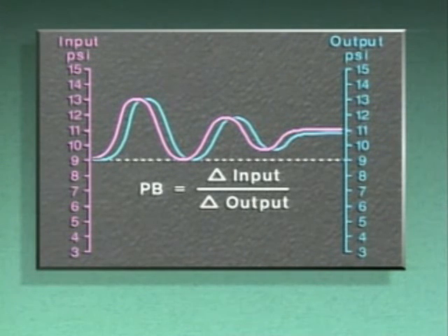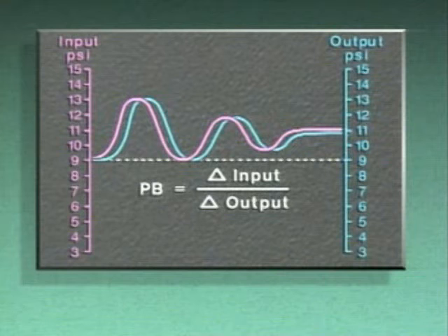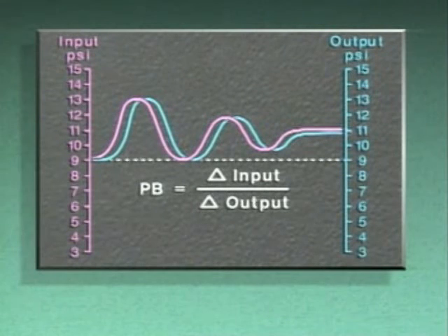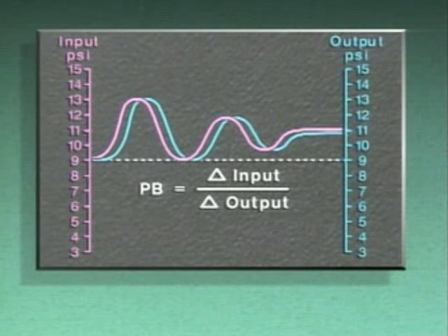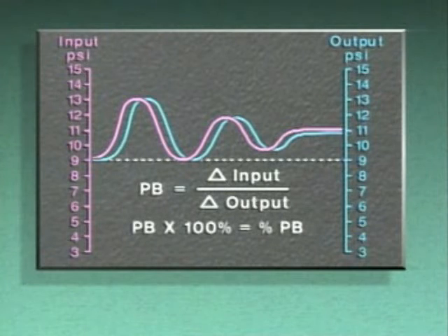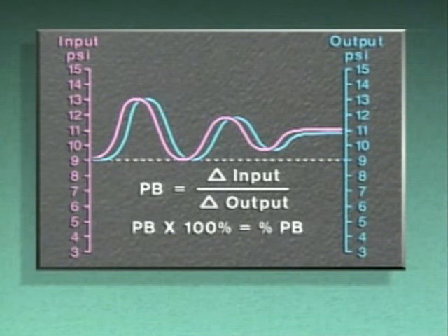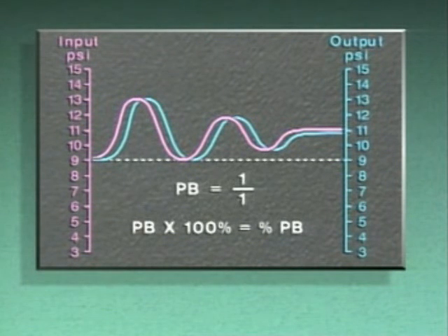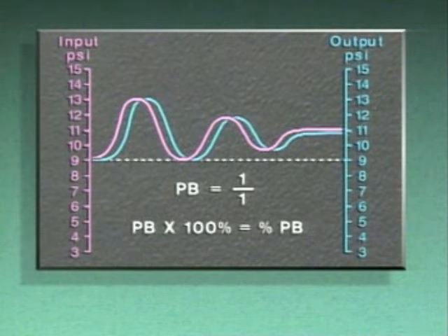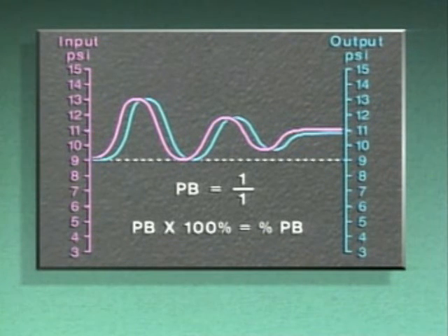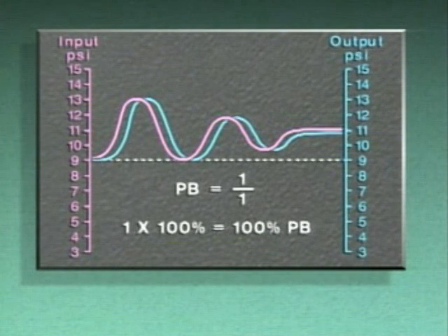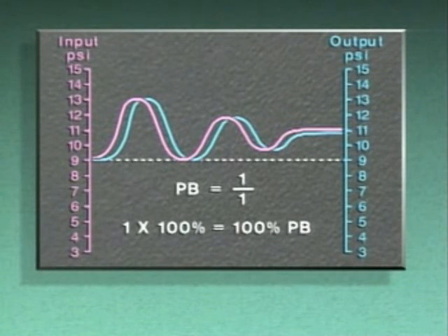Proportional band is the amount of output change, or delta output, in relation to a given amount of input change, or delta input. The proportional band value is usually multiplied by 100% so that it can be expressed as a percentage. When a controller's input change and output change are equal, the relationship between the signals is one to one, and the proportional band is 100%. This condition is called a 100% PB.